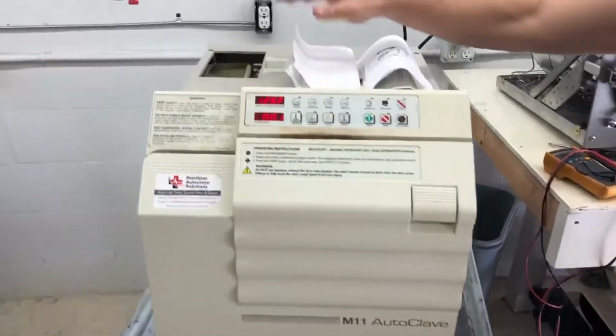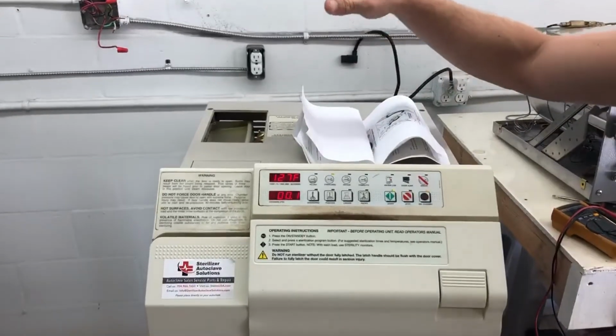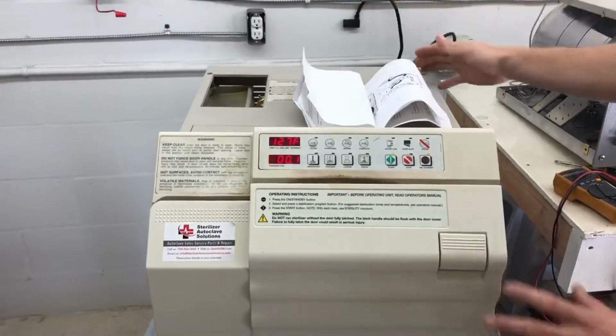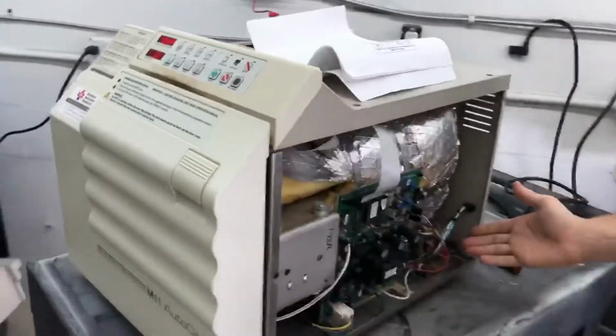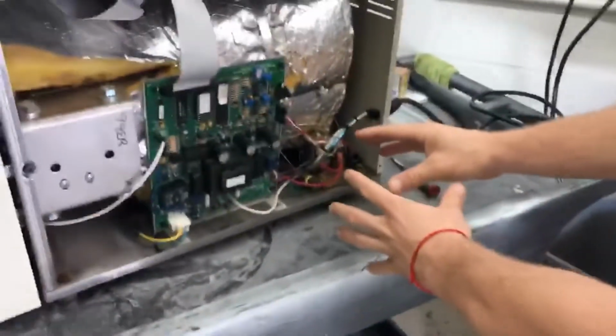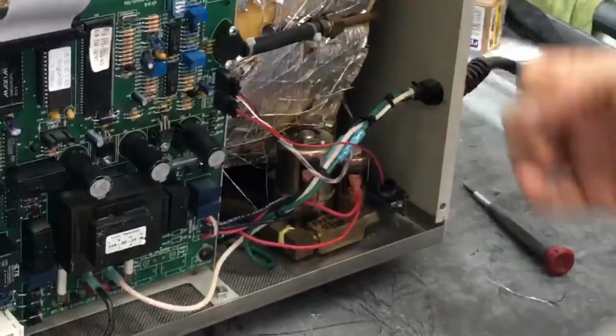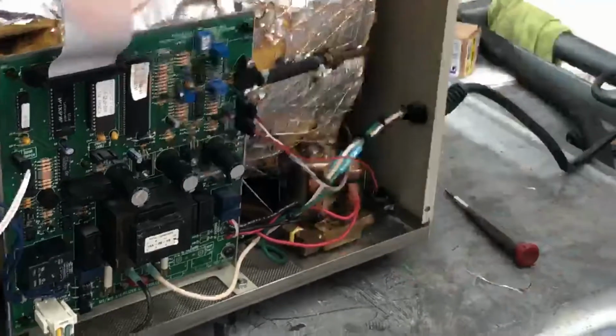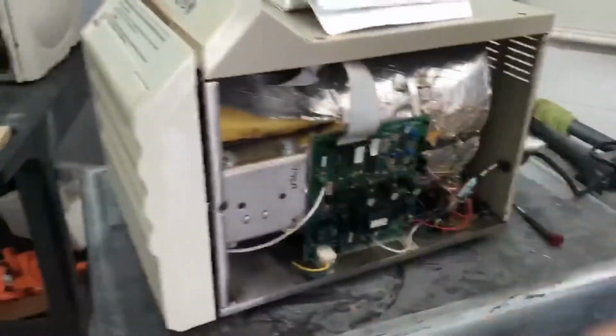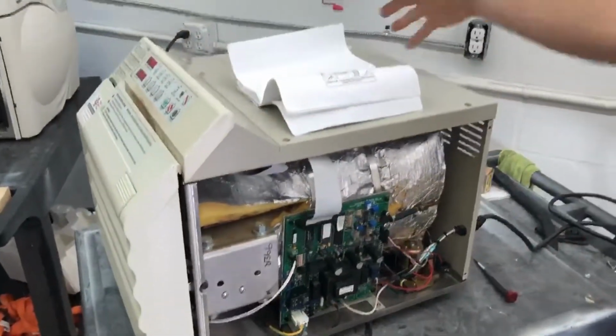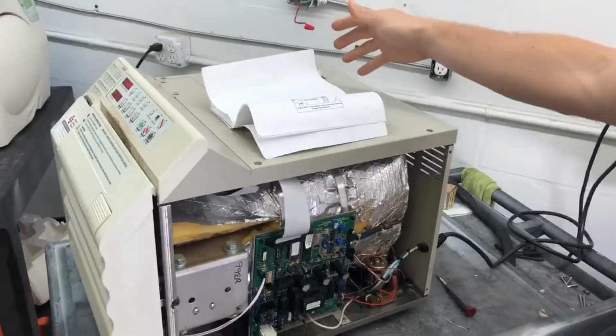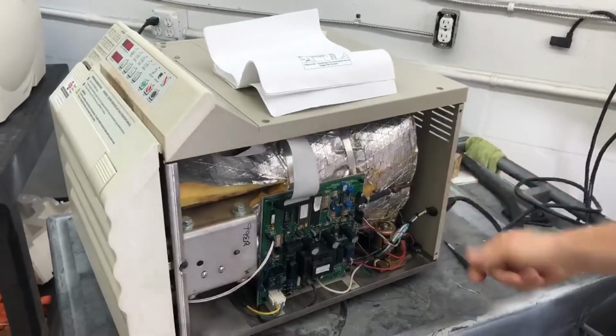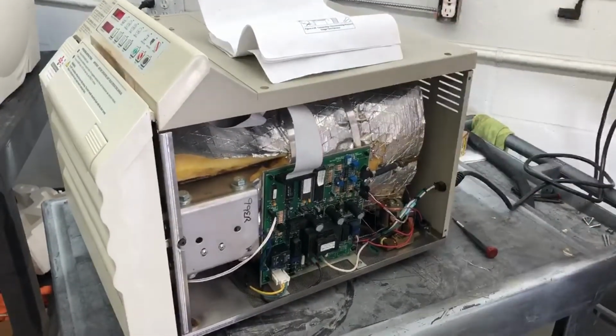The reservoir needs to be cleaned regularly. If you have buildup in the reservoir, it ends up getting into the valves and clogs them, which makes the machine not hold pressure. So you could be leaking at the door gasket, possibly. You could have dirt and buildup in your reservoir causing valves to stick and leak, causing it to fail.